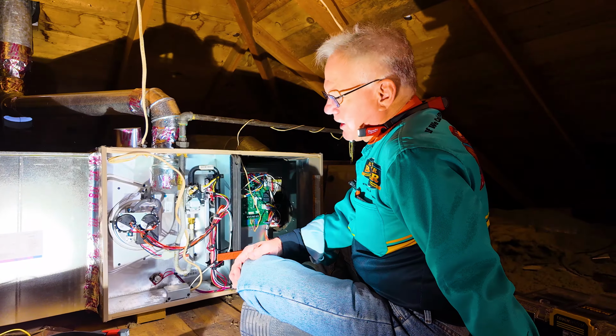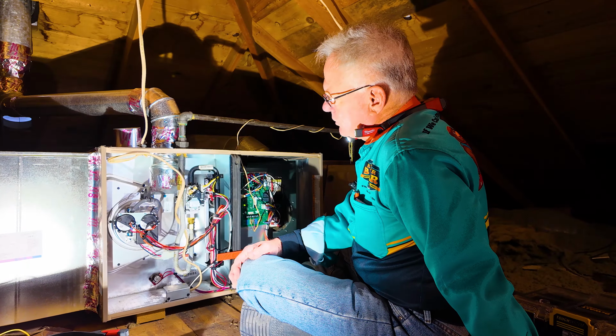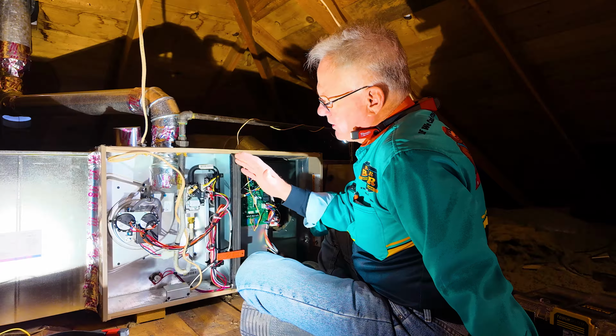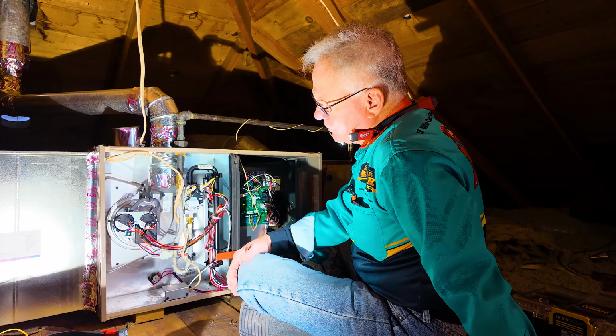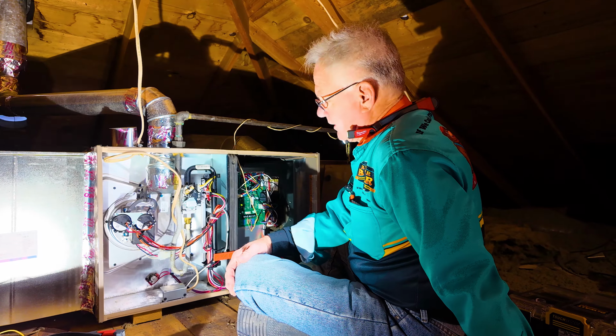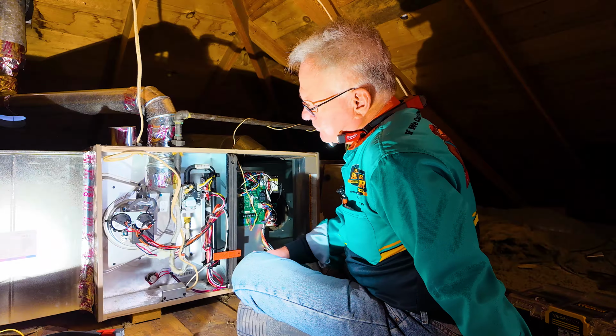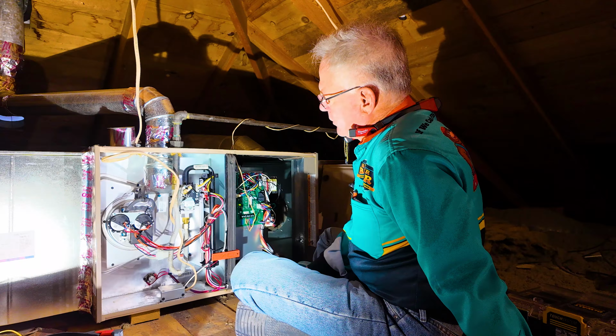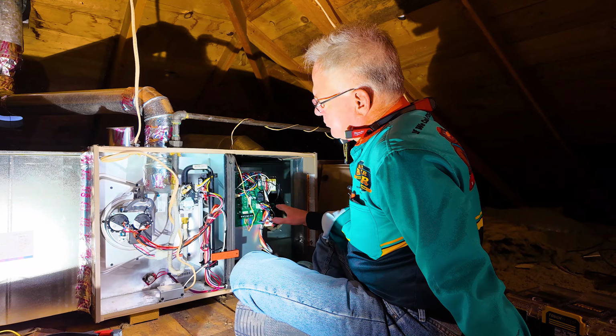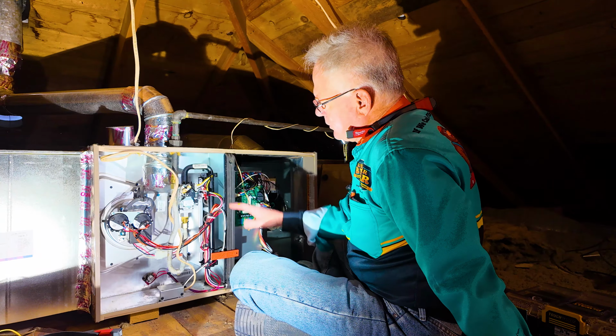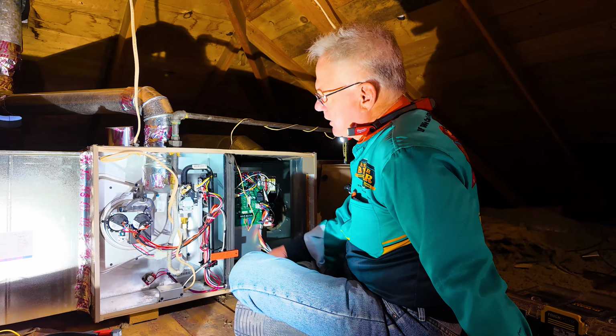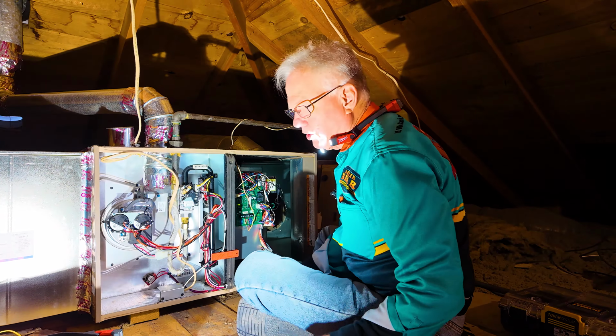And I'm wearing a carbon monoxide tester that is very sensitive, so there's no carbon monoxide being emitted here or in the unit, because I walked through the unit when it was running. It stayed in there quite a while, and if there was any carbon monoxide at all coming in, it would have registered. Okay, now the blower motor went off because the heat exchanger cooled down, and it's now on idle, standby, waiting for the next thermostat call.